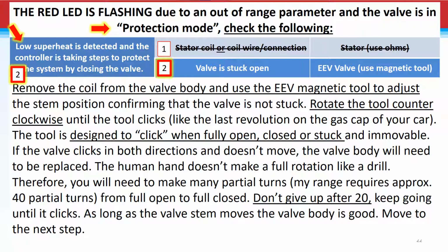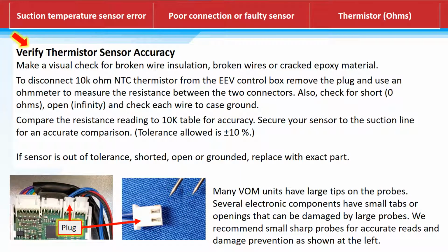The human hand doesn't make a full rotation like a drill. Therefore, you're going to need to make many partial turns. My range requires approximately 40 partial turns from open to full closed. So don't give up after 20 turns on that valve. Keep going until you get a click. As long as the valve stem moves, the valve body is good, so we can move on to the next step. Here we need to verify the thermistor sensor is operating accurately.